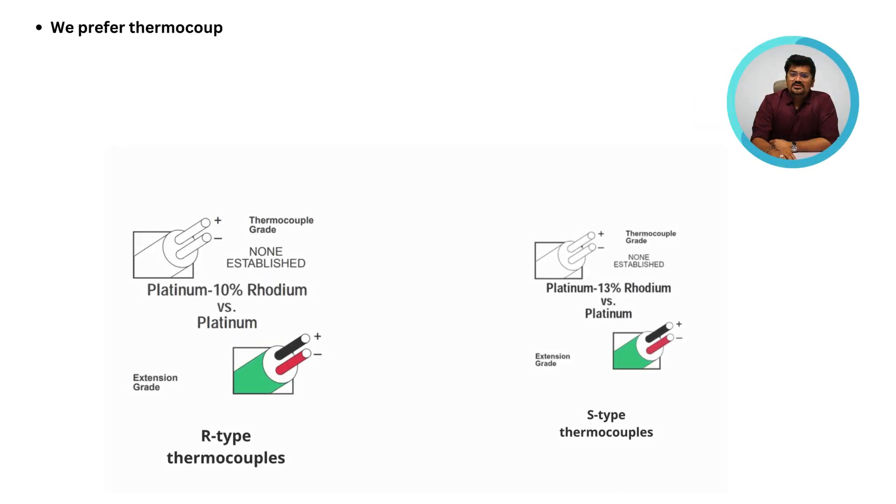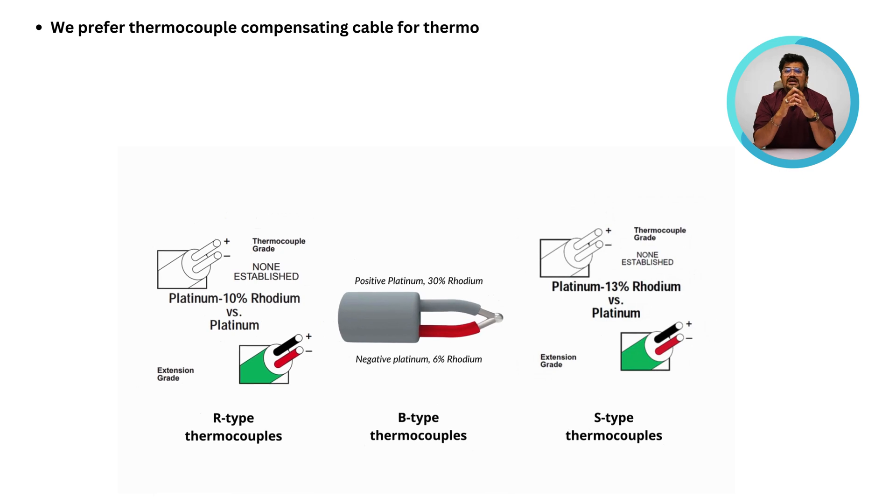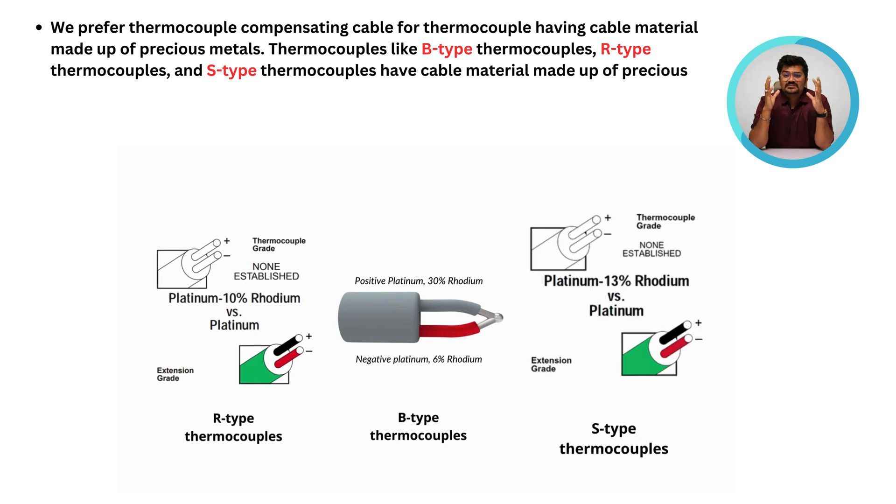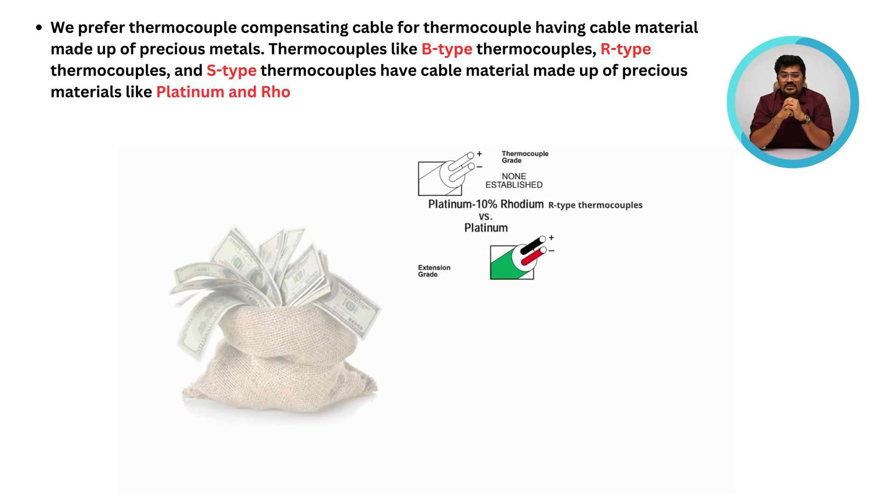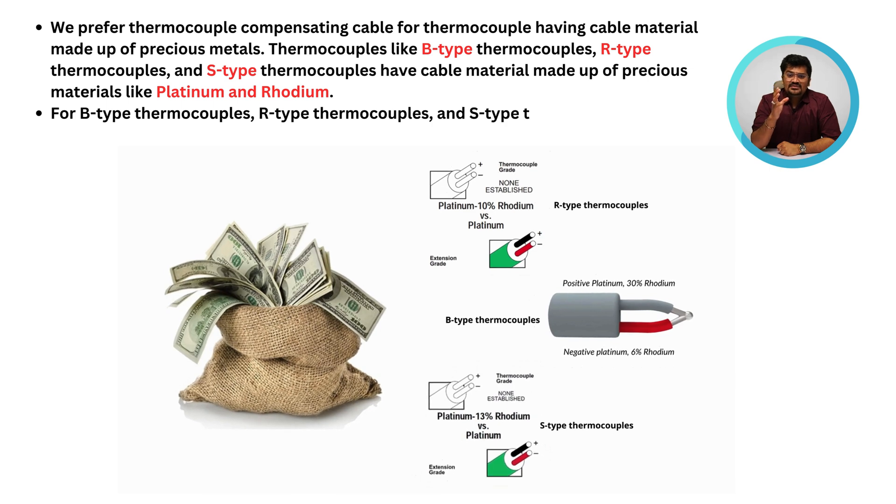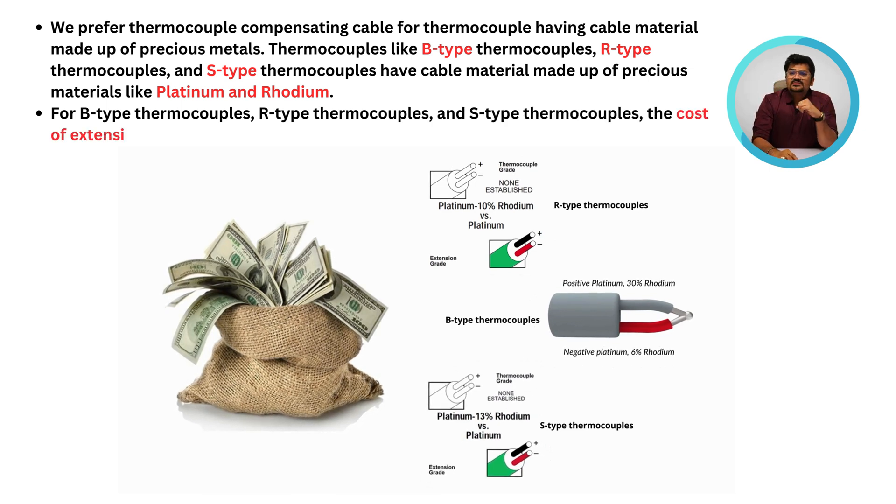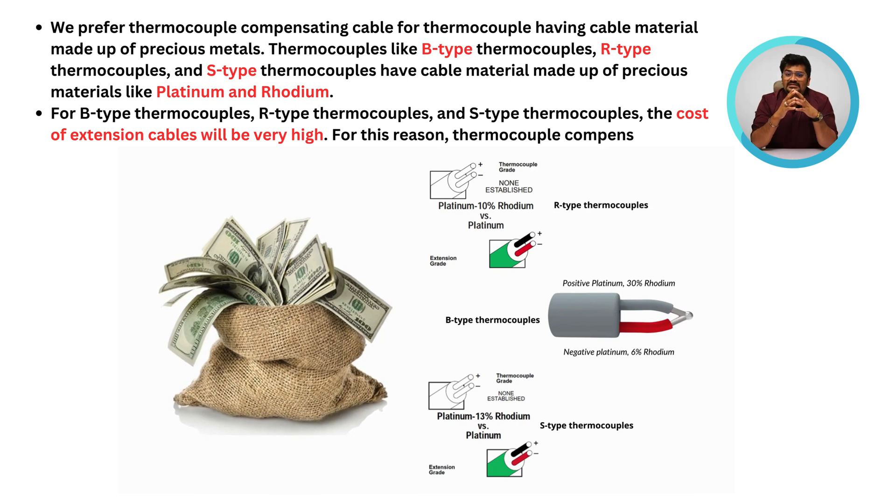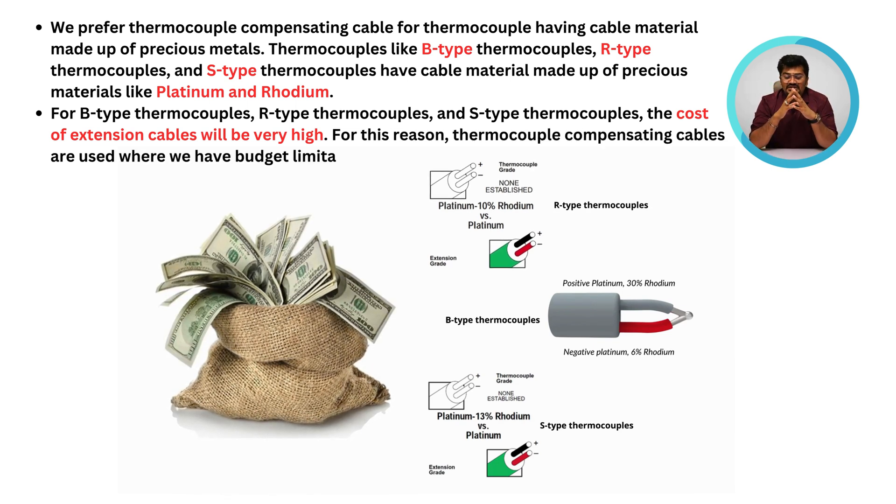We prefer thermocouple compensating cable for thermocouples having cable material made up of precious metals. Some examples are like B-type thermocouple, R-type thermocouple, and S-type thermocouple, which have cable material made up of precious metals like Platinum and Rhodium. For B-type, R-type, and S-type thermocouples, the cost of extension cable will be very high. For this reason, thermocouple compensating cables are used where we have budget limitations.